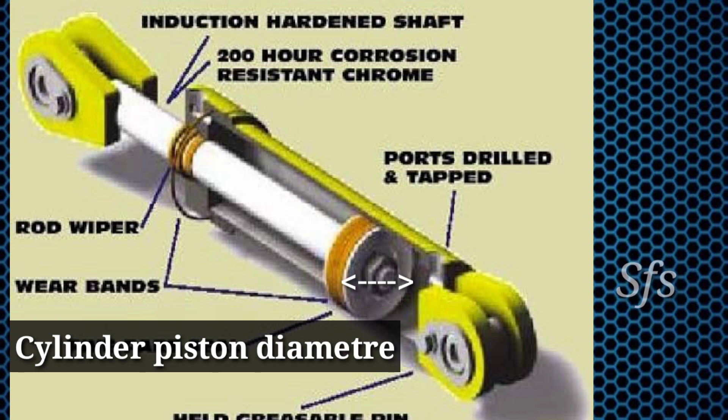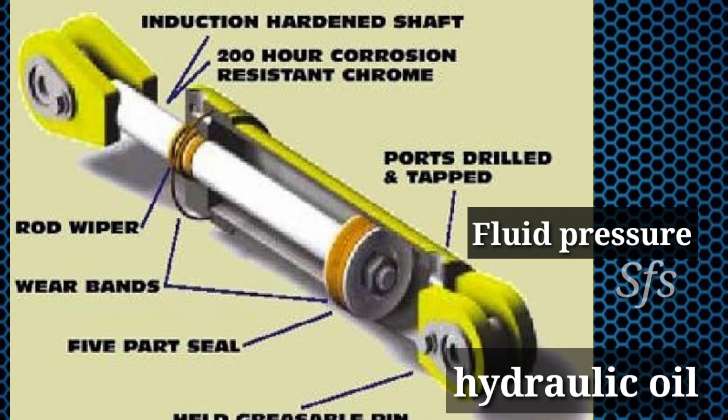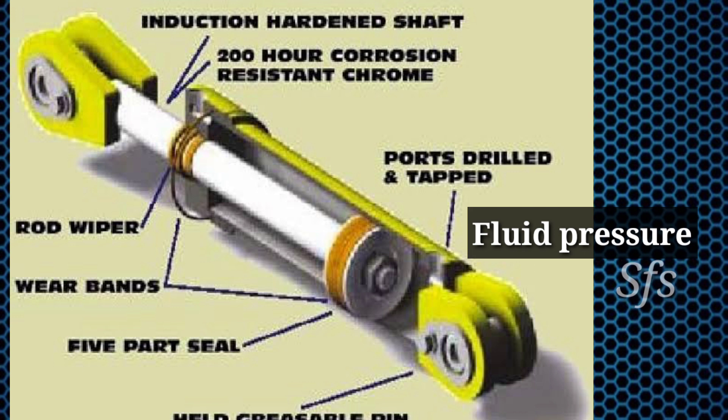To calculate force developed by any hydraulic cylinder, we require two things. First is cylinder diameter, with which we calculate the piston area, and second is fluid pressure. In hydraulic cylinders, hydraulic oil is used. For force calculation, we require the pressure of that fluid, and we can easily get the pressure from the pump.